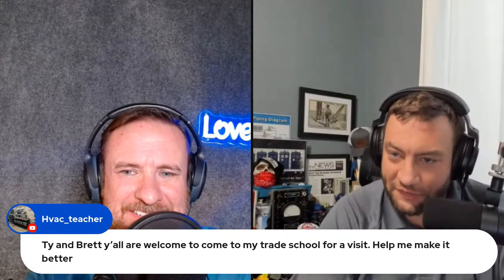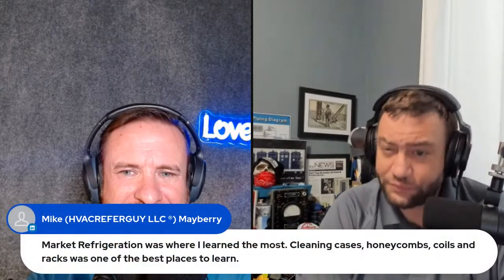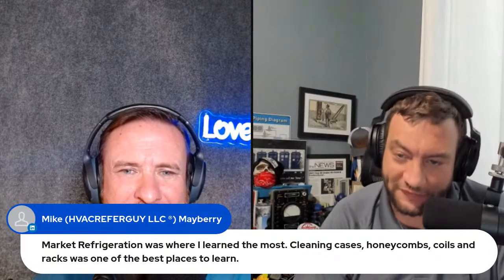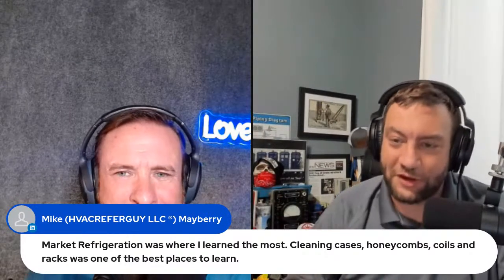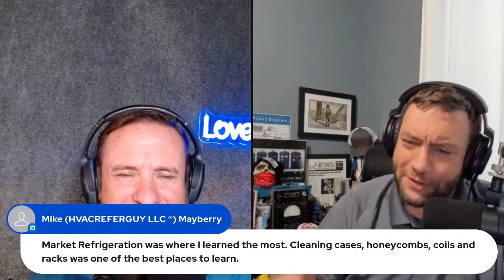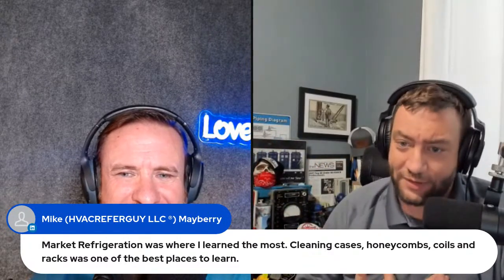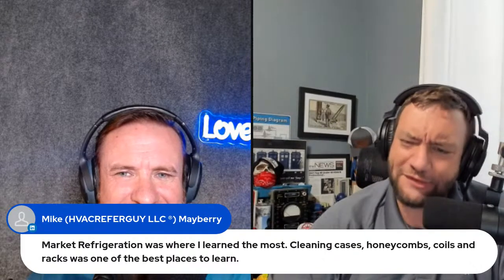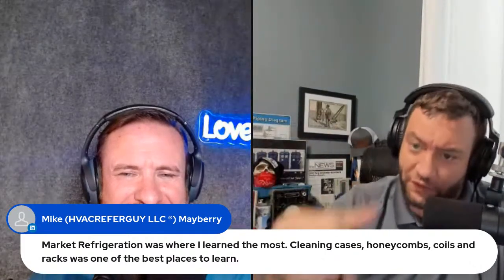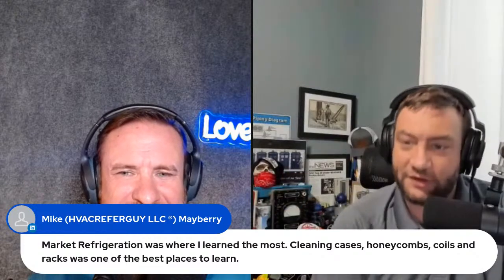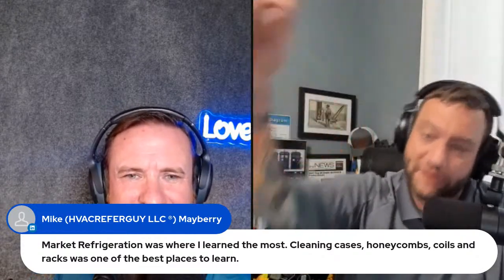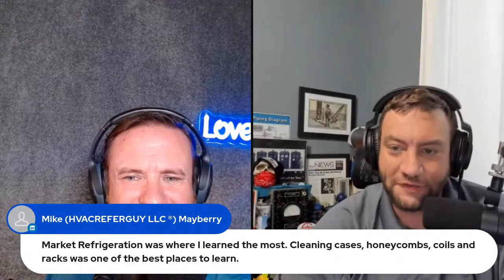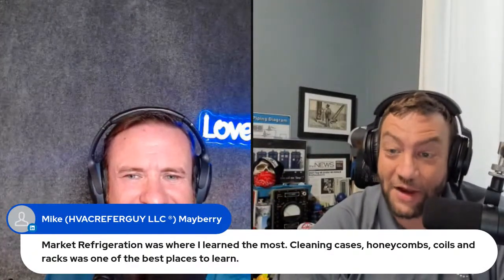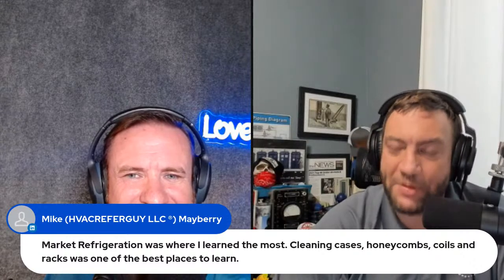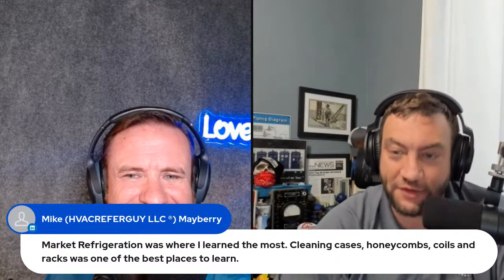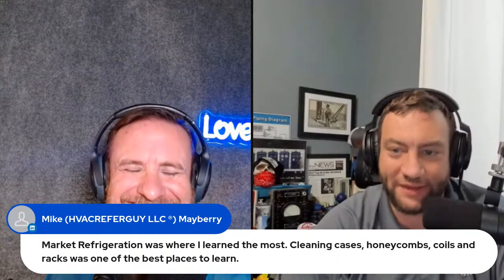The technician that was there, the original call was it wasn't feeding refrigerant. The solenoid was backing up, so he replaced the solenoid. I'm just looking around and I see - wow, that solenoid looks brand new. I'm like, I've never had one on my truck because they always have to order them. I said chances are, because when it goes into hot gas, it goes reverse flow. The hot gas gets dumped in the suction, comes back up through the liquid line solenoid backwards, and then back up to the liquid header. So as I'm staring at this thing, I realize it's nice and clean, and I'm like, I bet you any money this dude put in a regular standard guts on that solenoid. That's probably why it's not feeding.